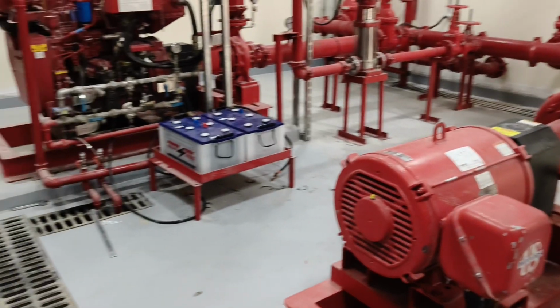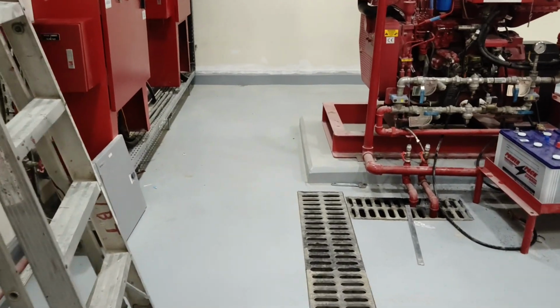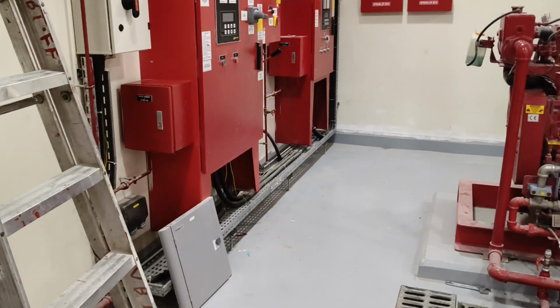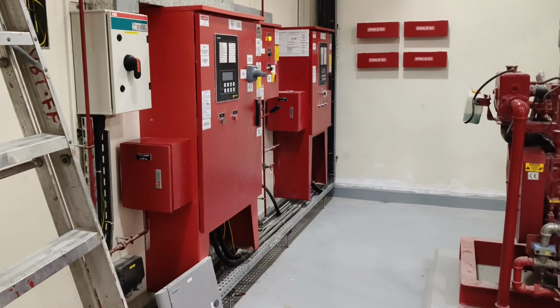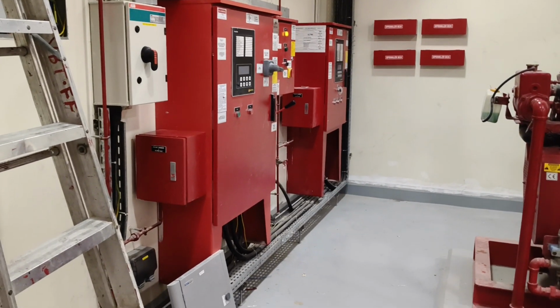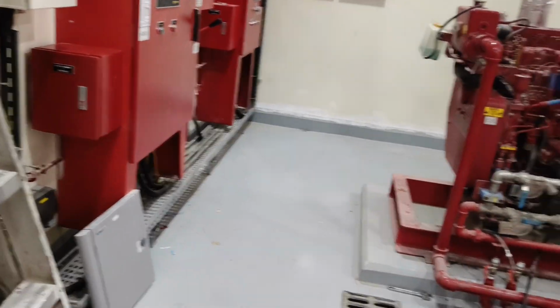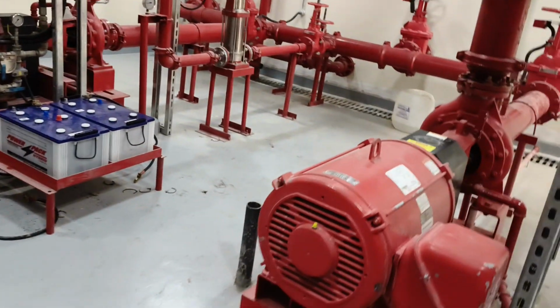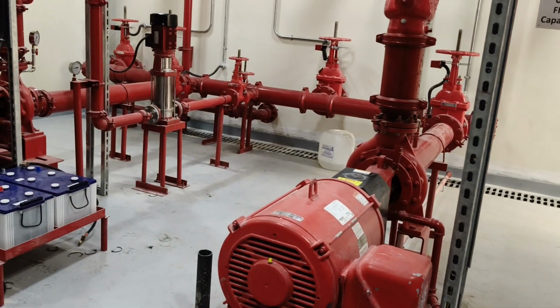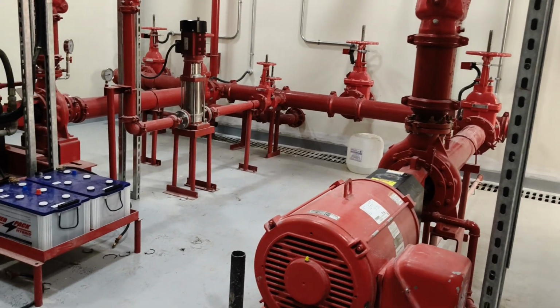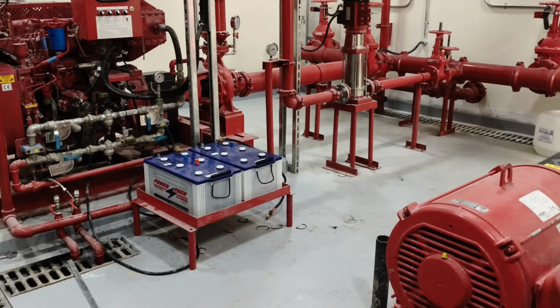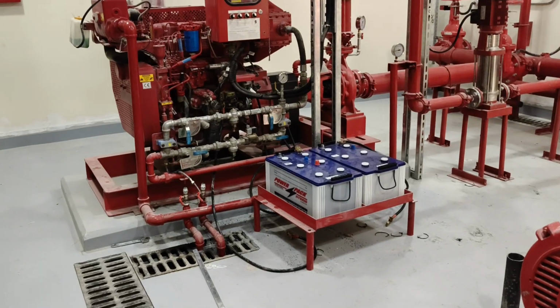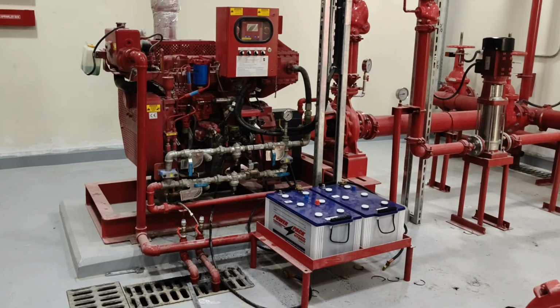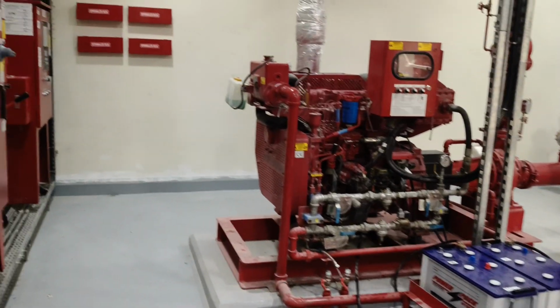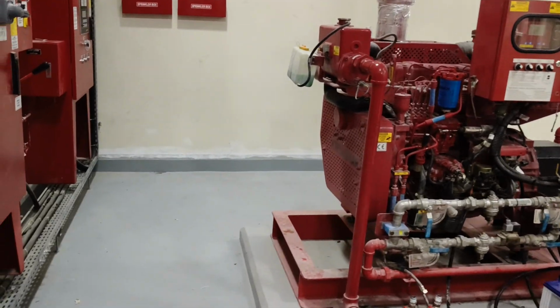Now with the cable tray, since the panels and controllers are down, many would have suggested that we should put the cable tray down, which is what most people do. They would tell you to fix it on the ground after putting a cover, which is also allowed, but it's supposed to have a clearance, like a 12-centimeter clearance.